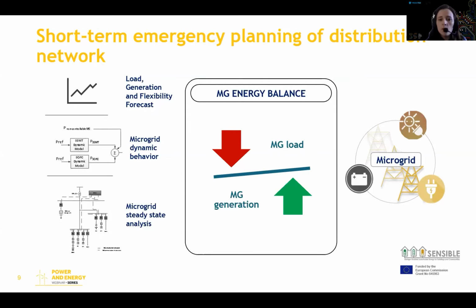So we developed what we call this short-term emergency planning tool that, based on the forecast for the next hour, tries to dispatch all the resources of the microgrid and the distribution system to ensure a secure islanding, and then to ensure that the system is able to operate islanded during a given time. Okay, in this case, we consider an hour.